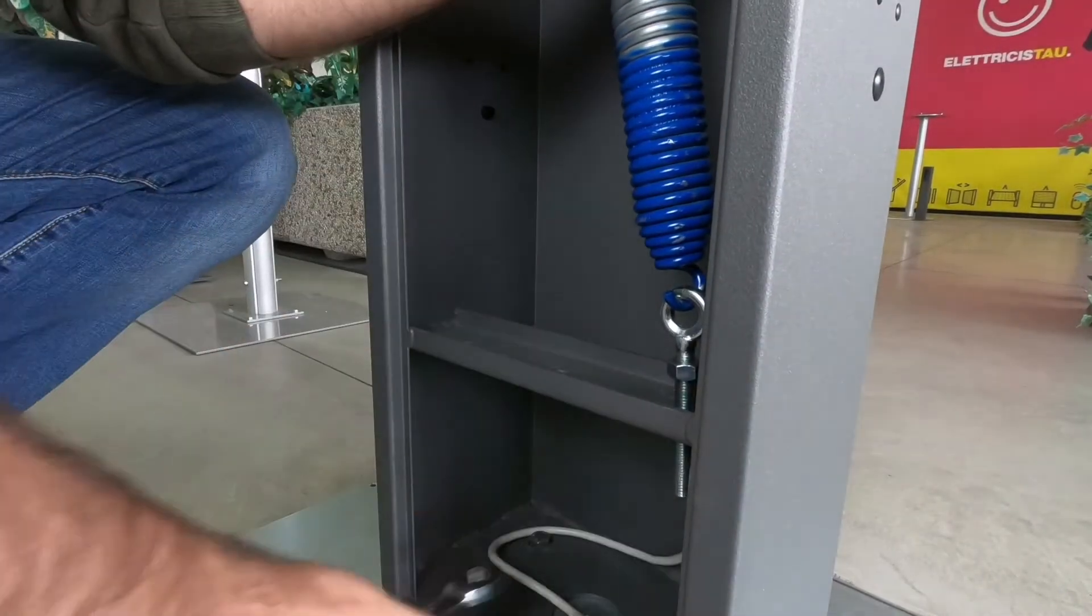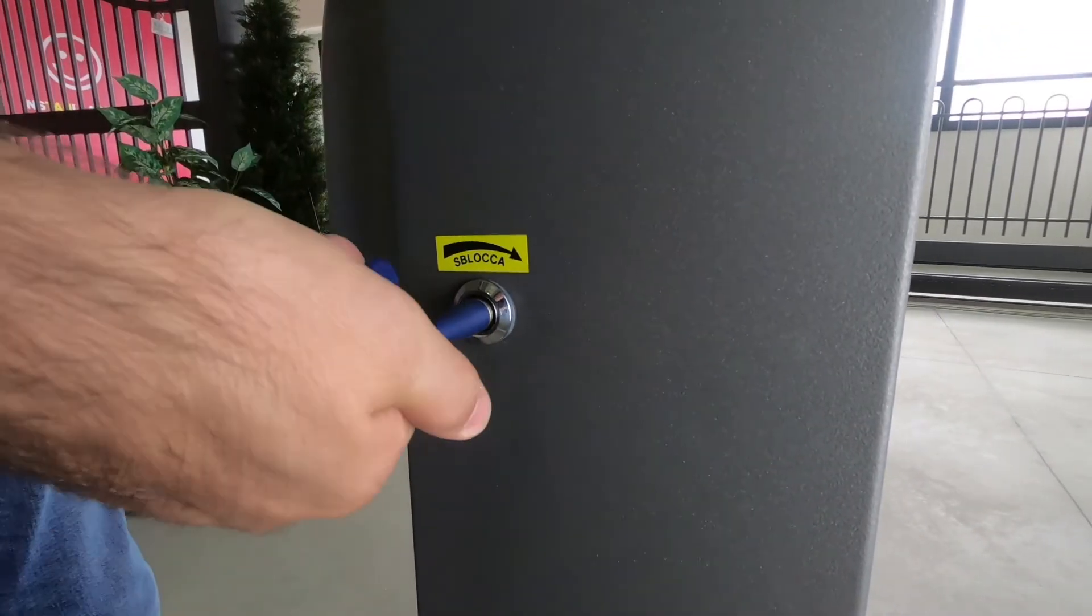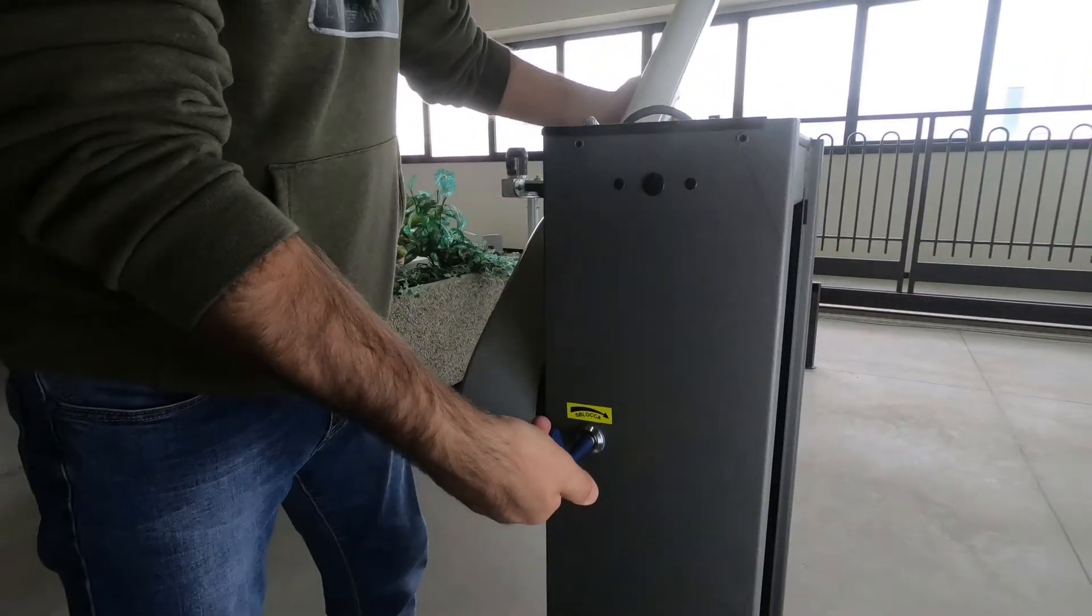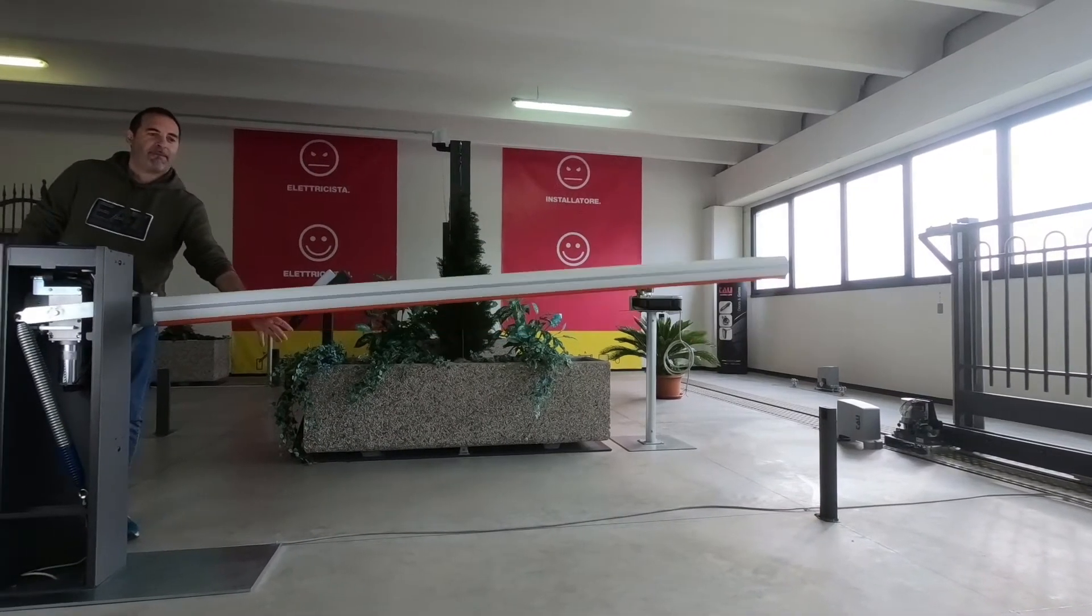To check if the spring has been correctly loaded, unlock the boom using the key and lower it manually until it's completely closed at zero degrees. When releasing the boom, it will have to raise itself and stay at about 45 degrees.